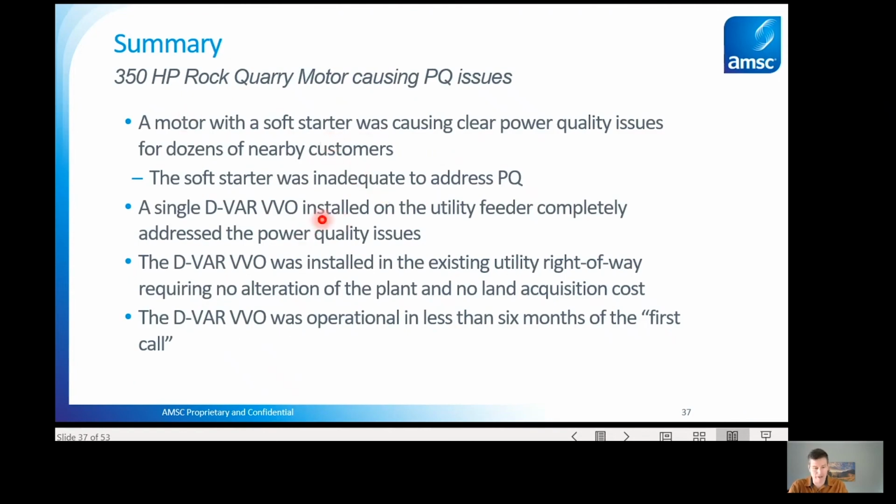So just a quick summary of this. There was a motor with a soft starter at a quarry causing power quality issues for dozens of customers. These customers were complaining of dimming lights as well as noisy appliances.